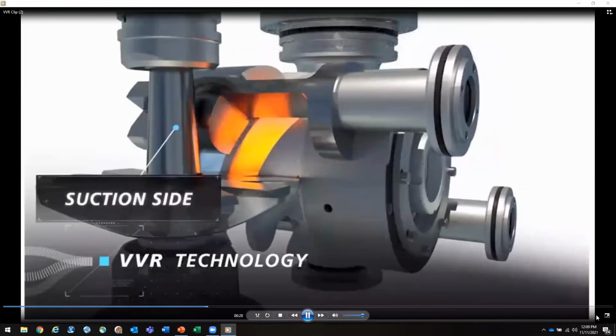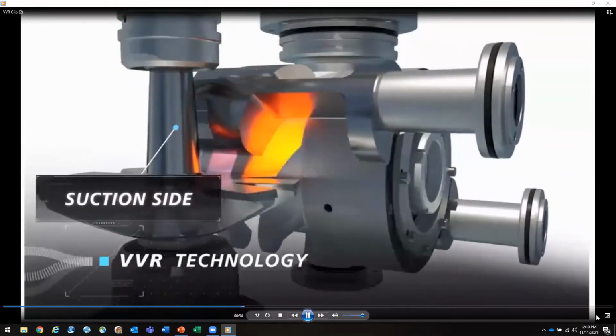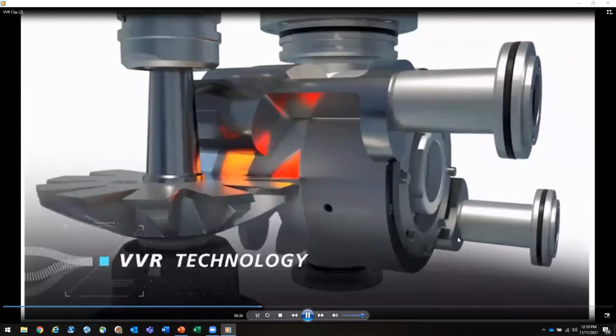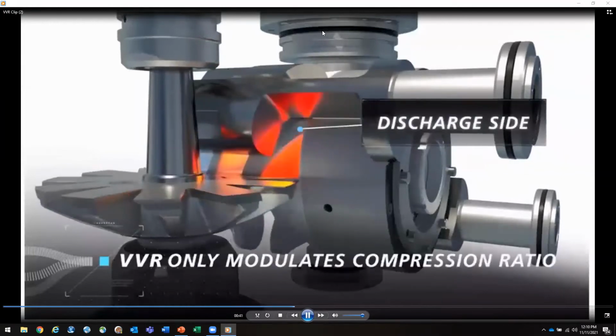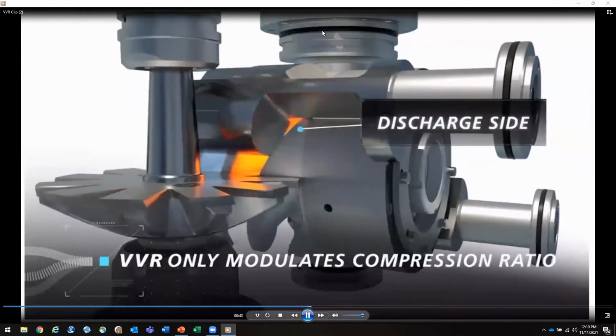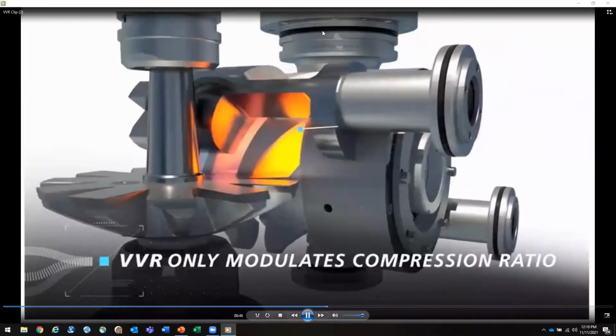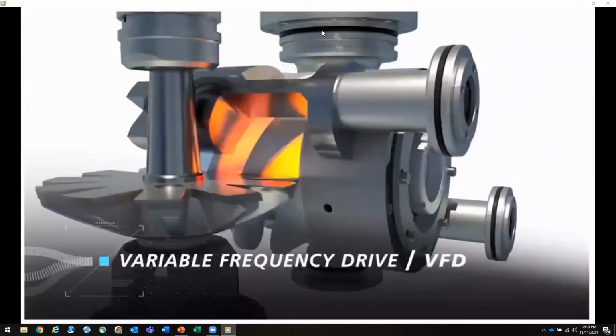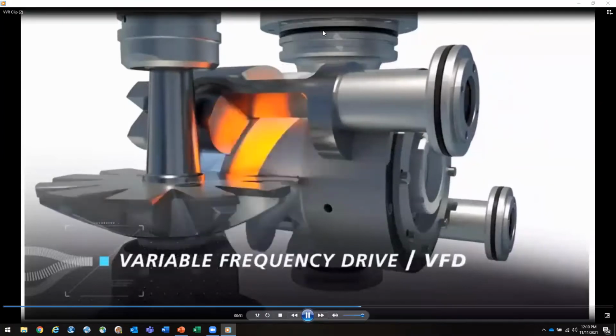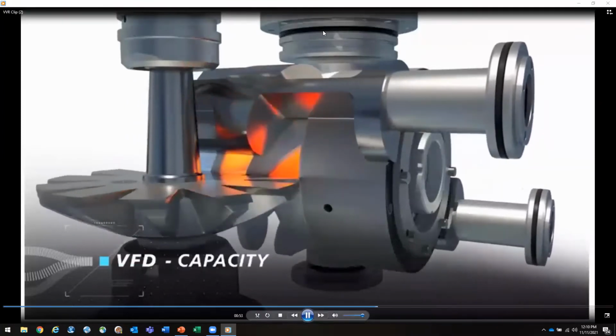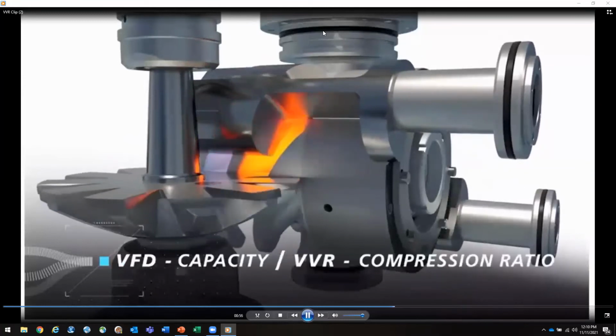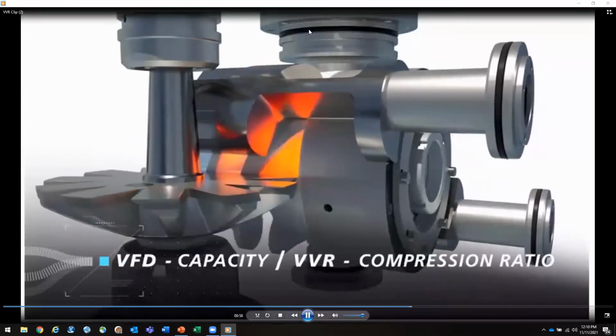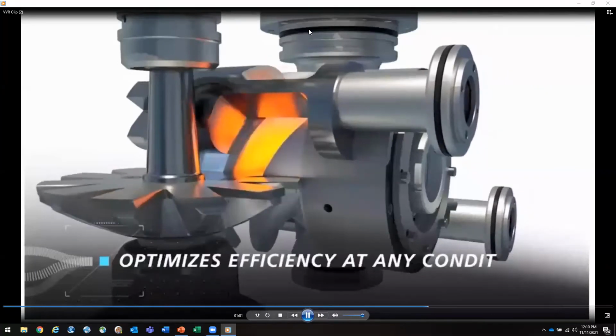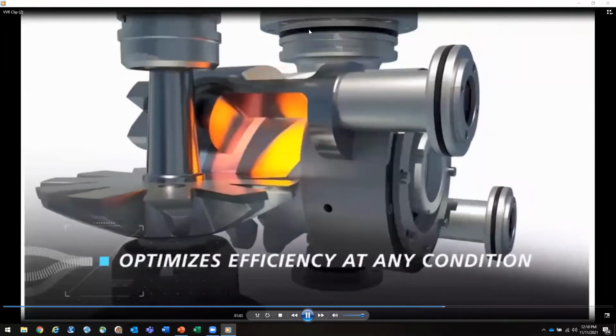Unlike a traditional screw that uses a slide valve on the suction side of the compressor that modulates capacity and does so less efficiently, VVR technology uses a slide on the discharge side of the screw, which does not modulate capacity at all, only compression ratio. Rather, capacity is controlled through use of a variable frequency drive. The combination of a VFD to control capacity and a VVR slide to control compression ratio works together synergistically to optimize efficiency at any condition.